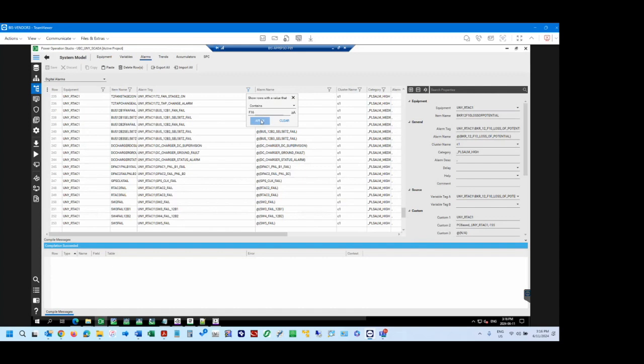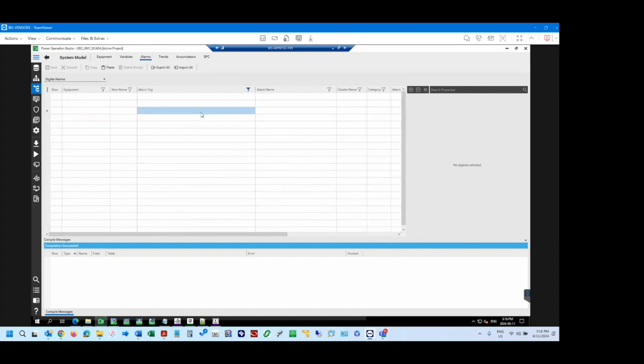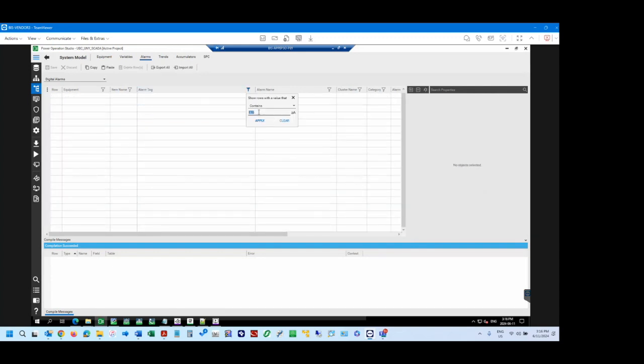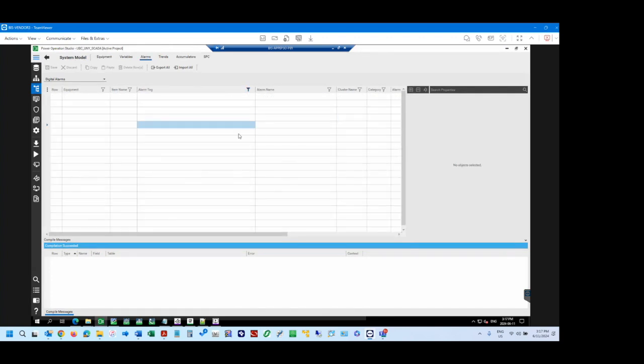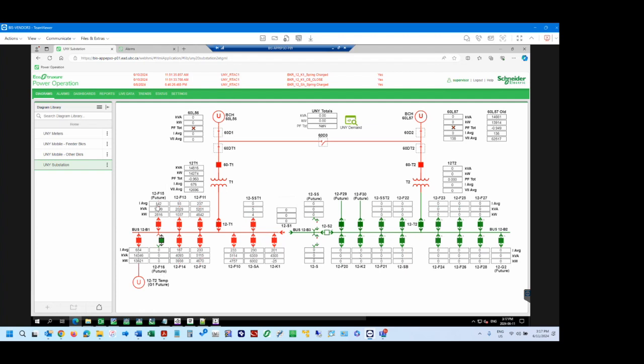So that's 16, you said? Yeah, F16 and now also F15 from earlier this week. That would be why, because we don't have them as tags right now. I didn't know that you guys were going to be using them because we had them qualified as future. Because they were labeled as future, I thought not to enable alarming on them yet. If you guys are actively using them right now, then we should just enable them.